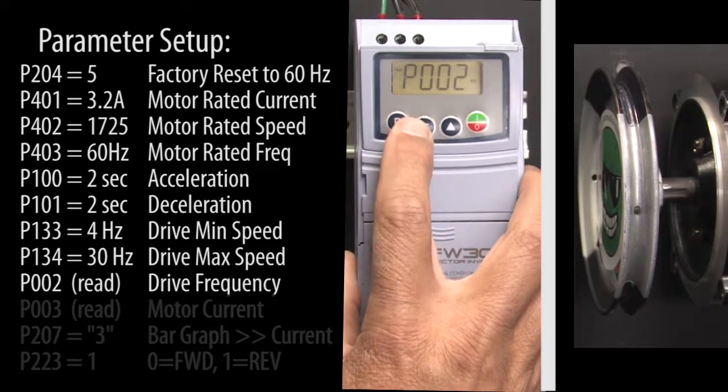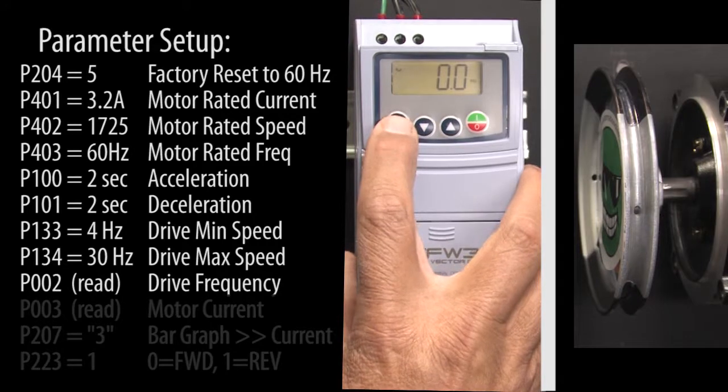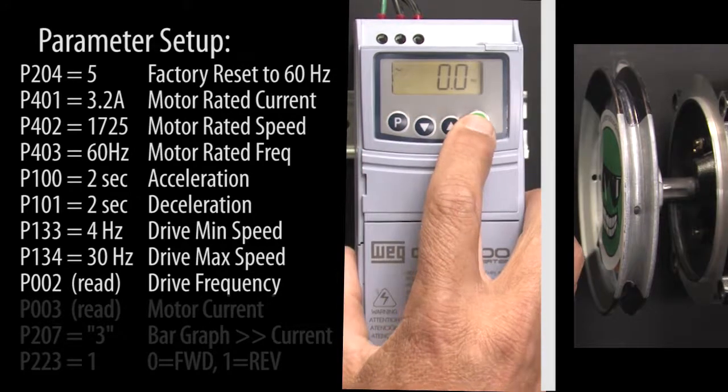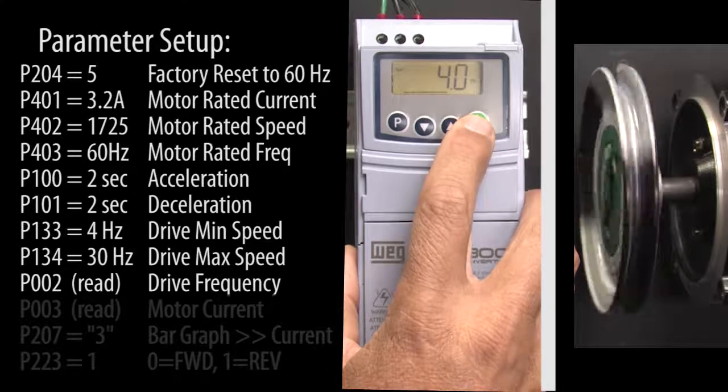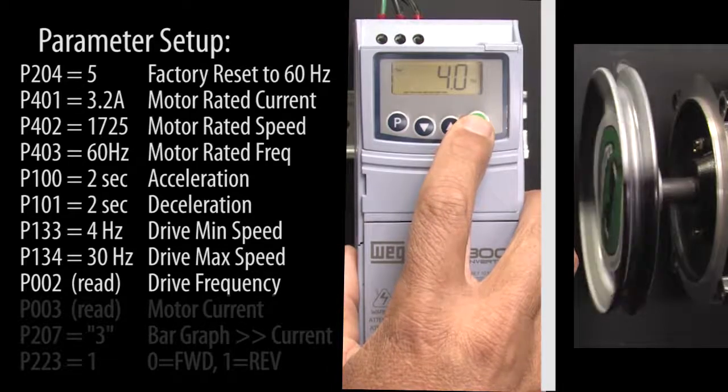Scroll to parameter 2 which shows us the drive's output frequency and press the run stop key to start the motor. And sure enough, the drive ramps the motor to the 4 Hz minimum output frequency we just entered. Perfect.